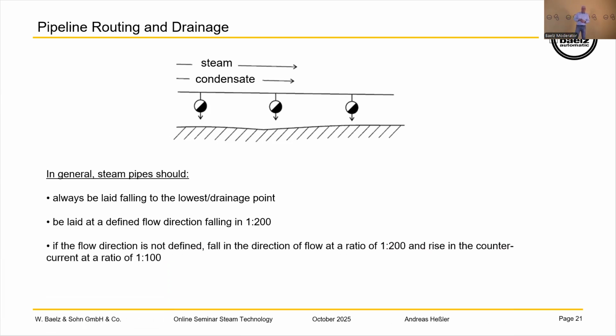And if the flow direction is not defined, you had better use it a little bit smaller when mounting the condensate valve, the condensate steam traps. Note for steam traps, when we have that much water inside the steam, I already told you to not have a steam velocity over 20 meters per second.